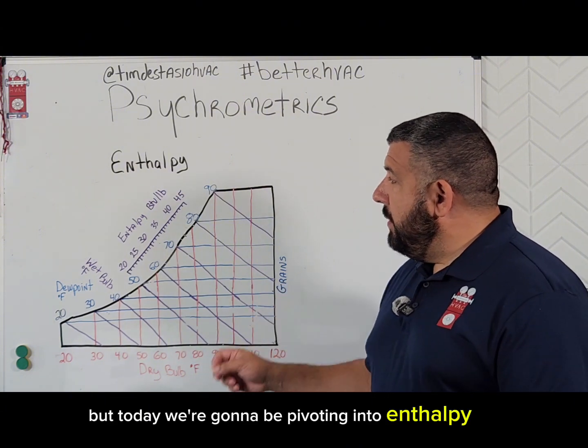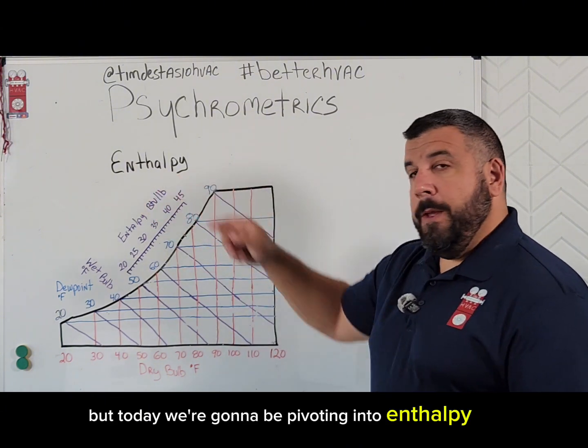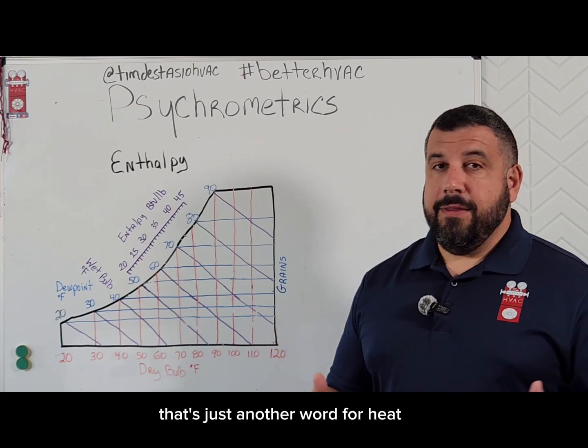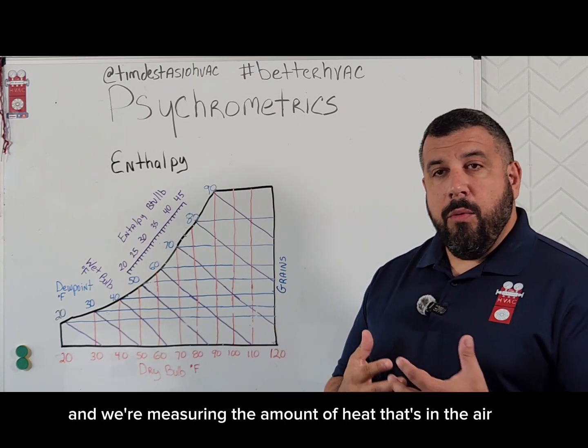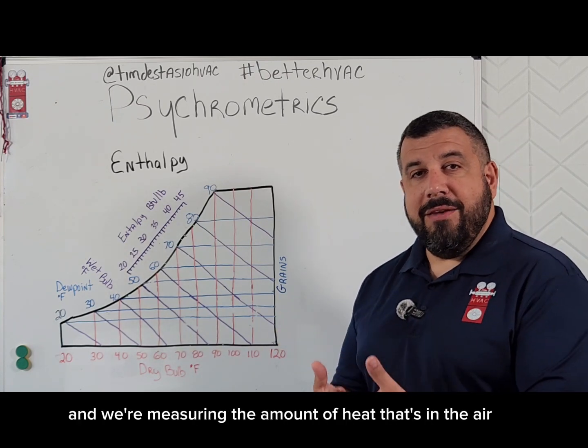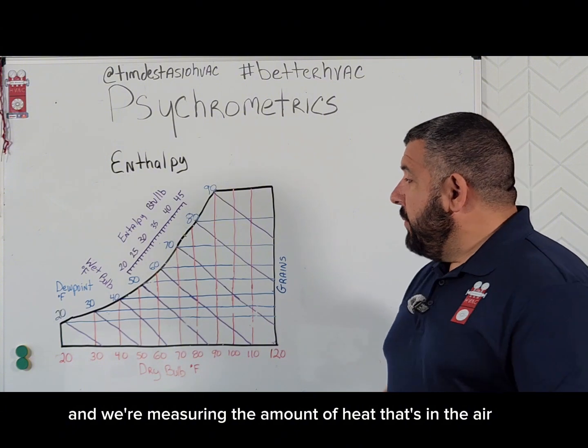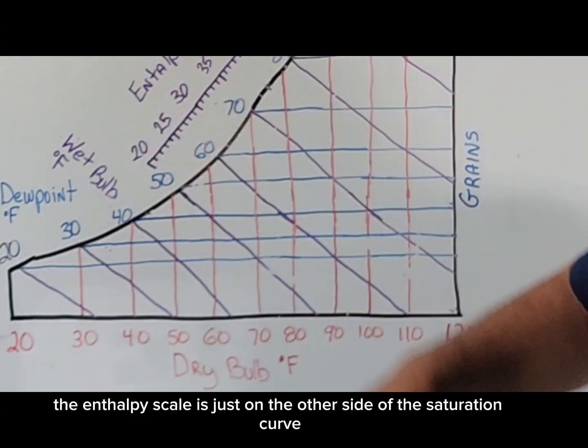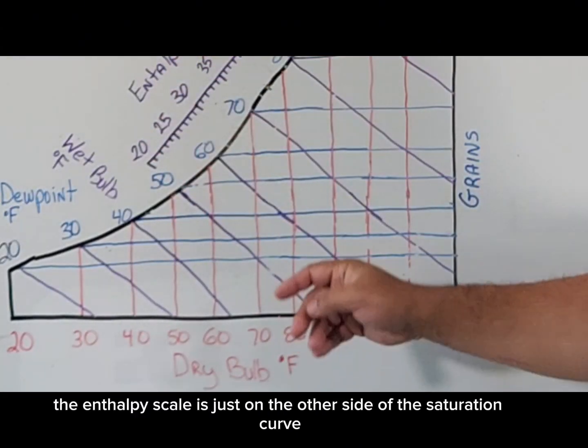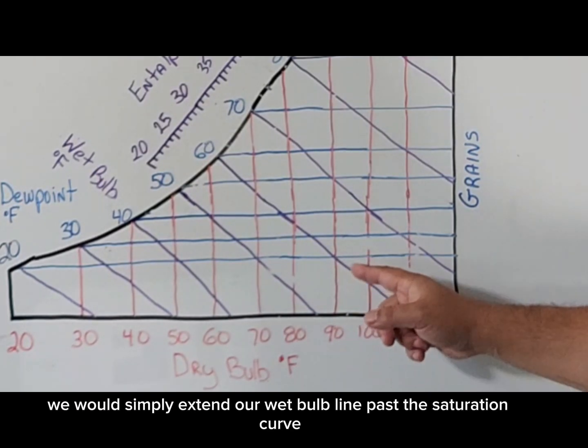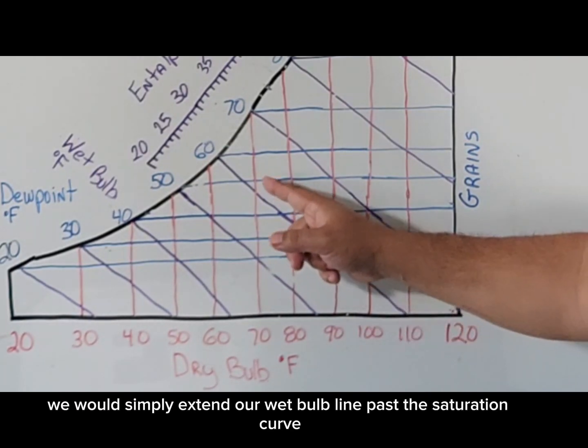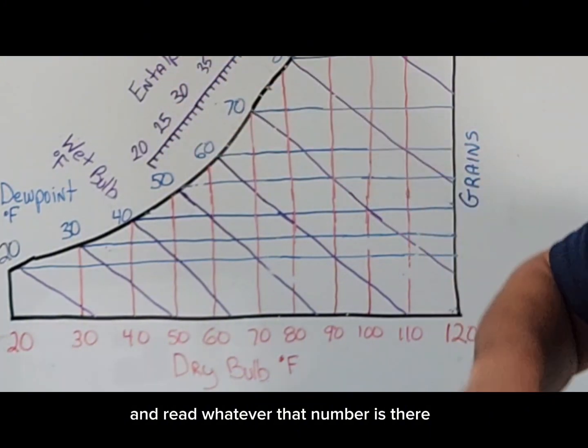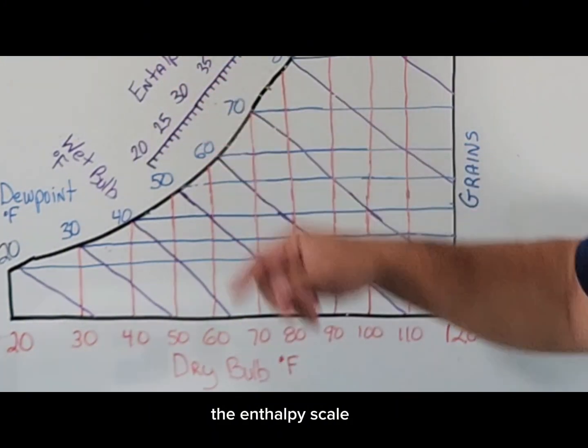But today we're going to be pivoting into enthalpy. What is enthalpy? Enthalpy is heat — that's just another word for heat — and we're measuring the amount of heat that's in the air. Now the enthalpy scale is just on the other side of the saturation curve. So in order to read that, we would simply extend our wet bulb line past the saturation curve and read whatever that number is there in the enthalpy scale.